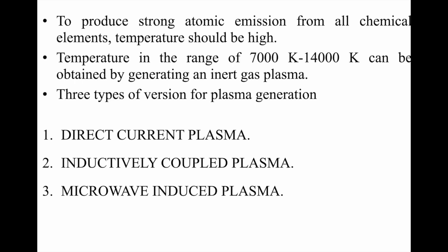To produce strong atomic emission from all chemical elements, temperature must be very high. Temperatures in the range of 7000 to 14000 Kelvin can be obtained by generating an inert gas plasma. There are three versions of plasma generation: direct current plasma, inductively coupled plasma, and microwave induced plasma.